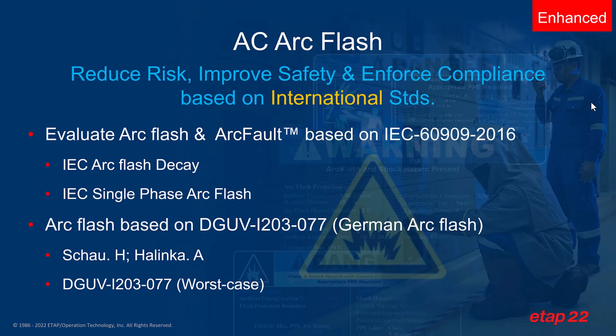ETAP 22 also has significant improvements to AC arc flash. AC arc flash allows us to reduce risk, improve safety, and enforce compliance. And you can do so now based on international standards. You can evaluate arc flash and arc fault based on IEC 60909. That includes the arc flash decay as well as single phase arc flash calculations. And you can also run arc flash simulations based on DGUV or the German arc flash standard. These options are essentially available in the arc flash study case for you to choose between different methods.